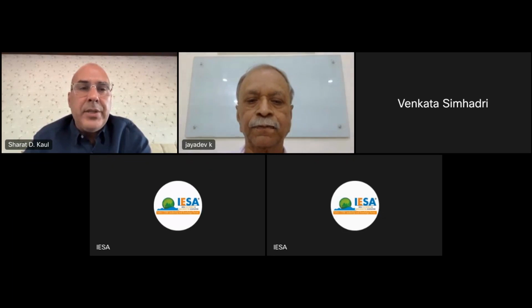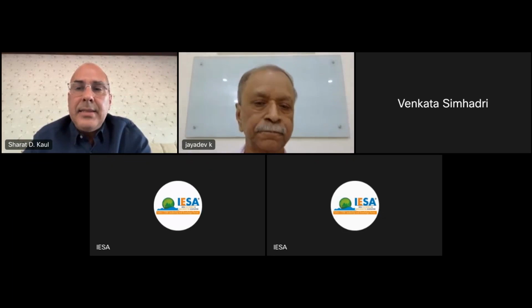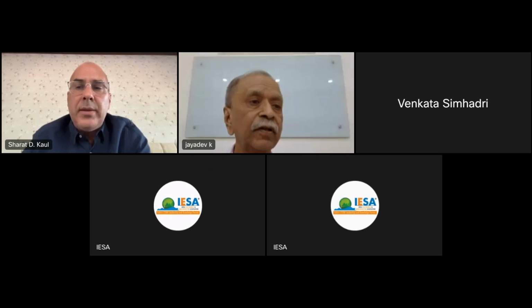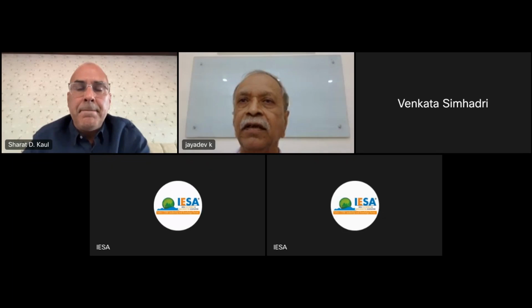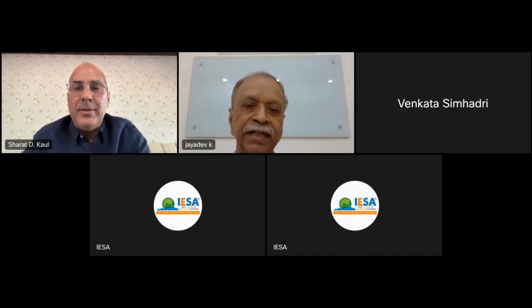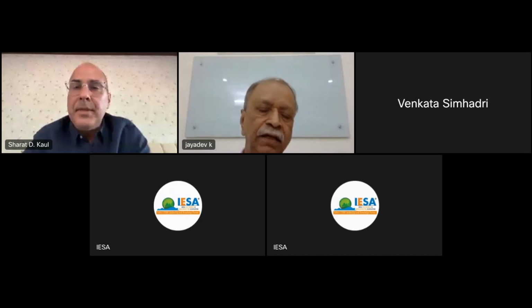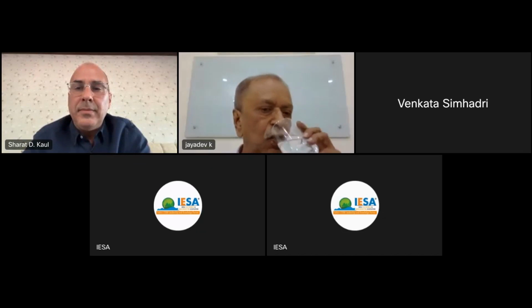Rajesh had a follow-up question with regard to the ESD tiles. He asks, how can we clean those tiles? Is it a wet mop, or are there any other standard solutions? If you use a wet mop, since the floor is perforated, all the contaminants go down to the sunken floor below. It becomes contamination as well. They're not supposed to mop; you use vacuum cleaners. In fact, you have to suck it up. So the process is dry, with a dry vacuum cleaner.